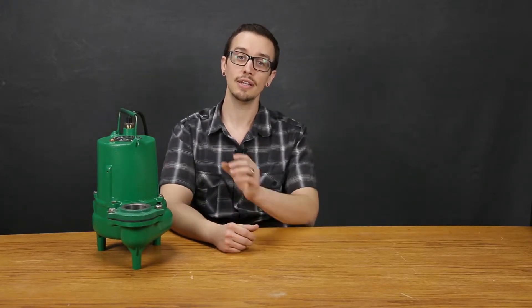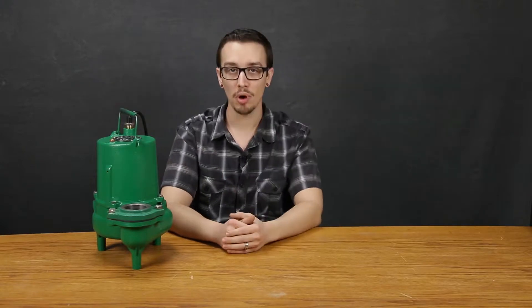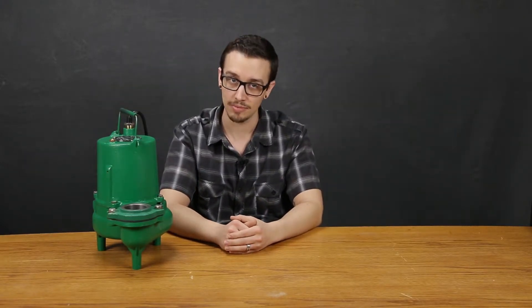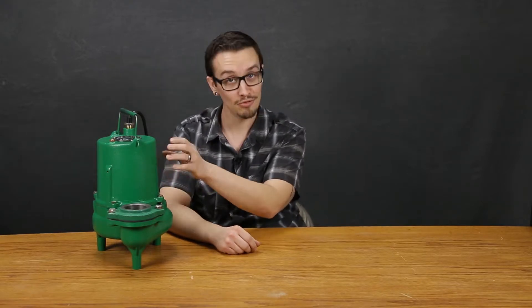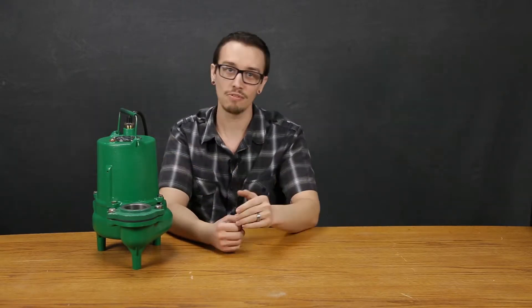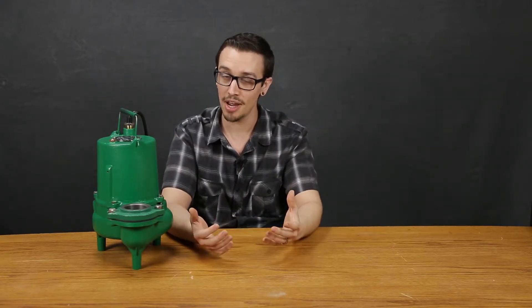In addition to this, a water-reducible alkaline enamel paint is applied to these pumps, which is a robust paint that holds up to harsh environments. The paint on this pump is between 3 to 4 mils thick, which is roughly 75 to 100 microns.